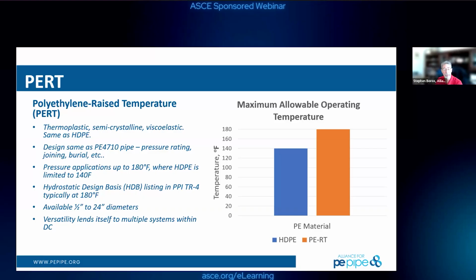Our normal HDPE for municipal applications can be used up to 140 degrees continuous long-term use. PERT can be used up to 180 degrees continual long-term use. So even within data centers, that covers a lot of the heat loop systems, especially bringing it from the CDU back out to the cooling towers. PERT could be perfect for that, and in fact it's used for that quite often. It's available from 1/2 inch to 24 inch, and it lends itself to a lot of applications—district heating, district cooling. That's where this little niche of PERT really shines.